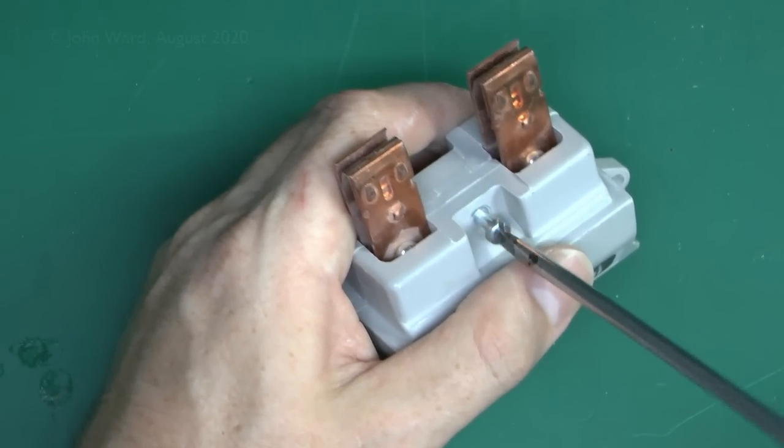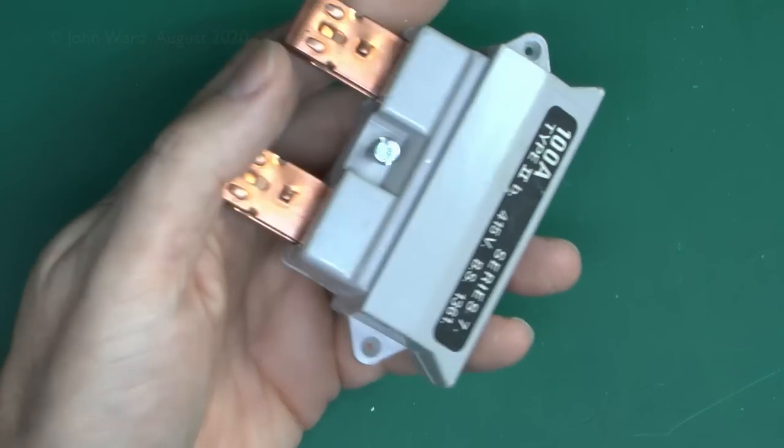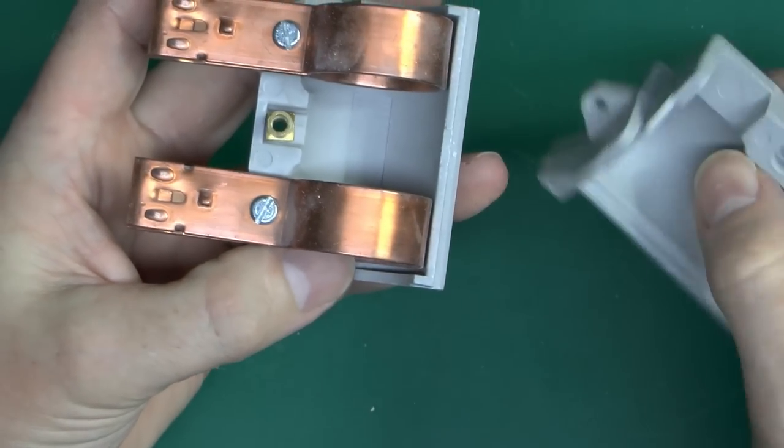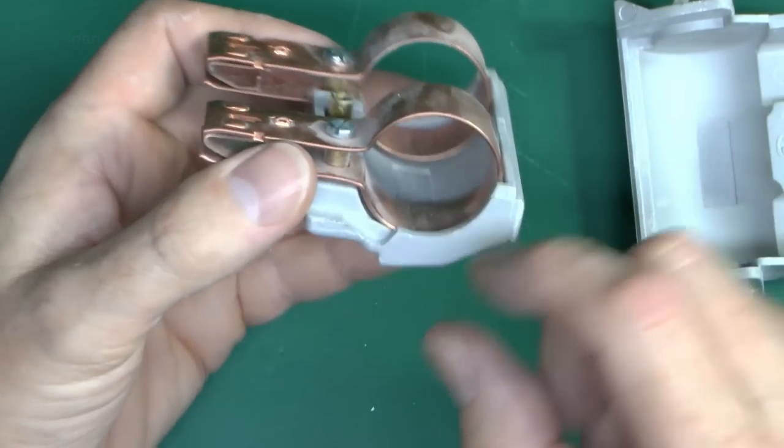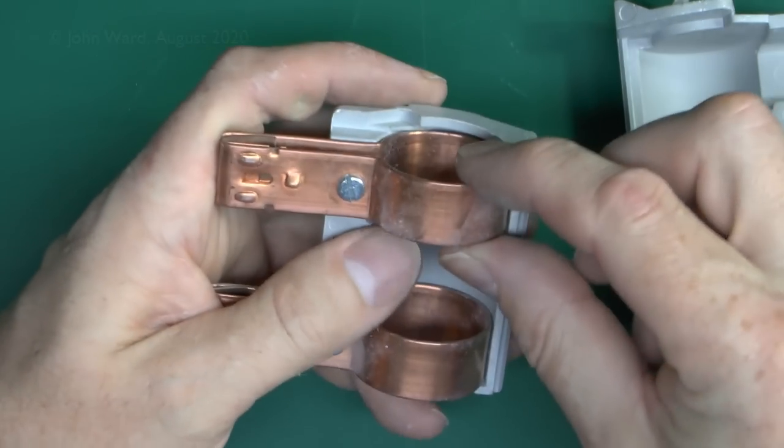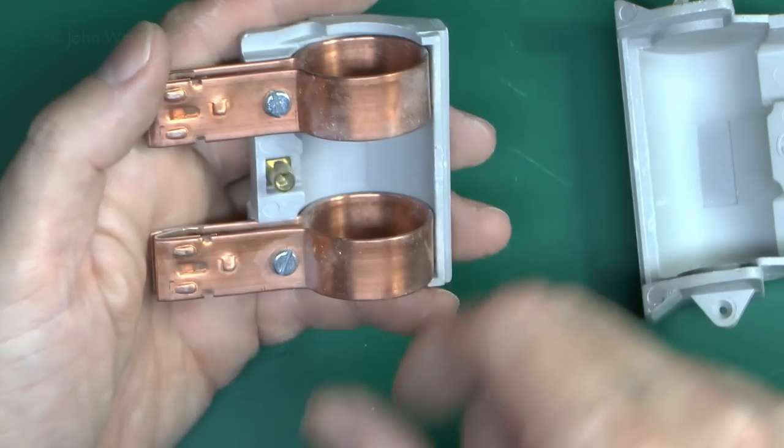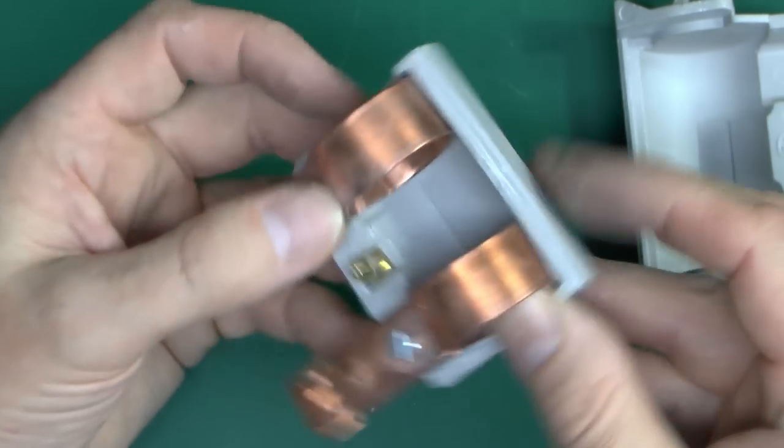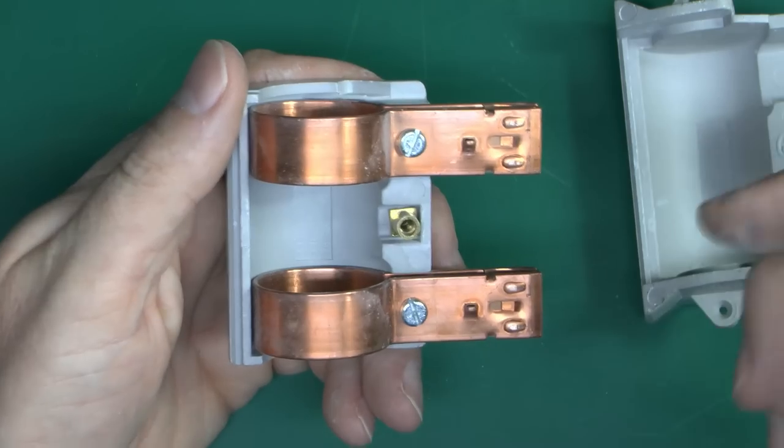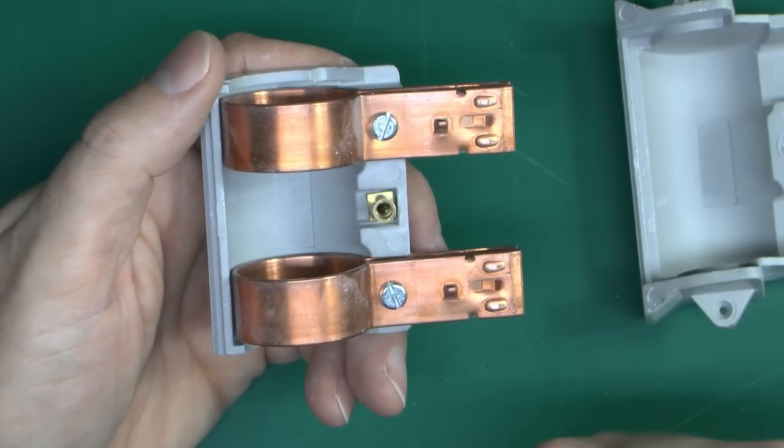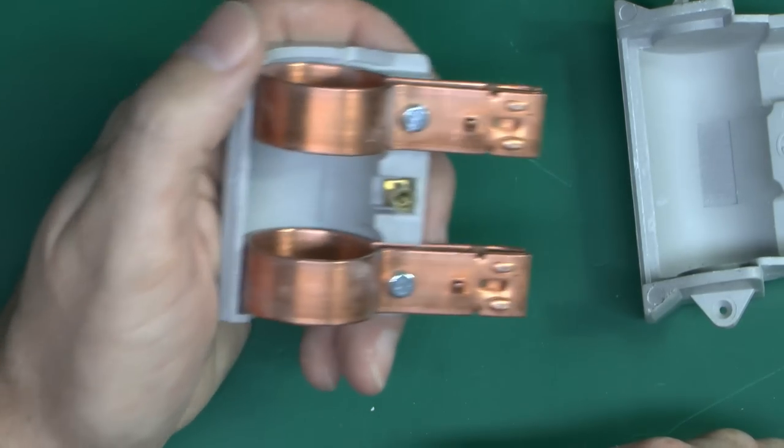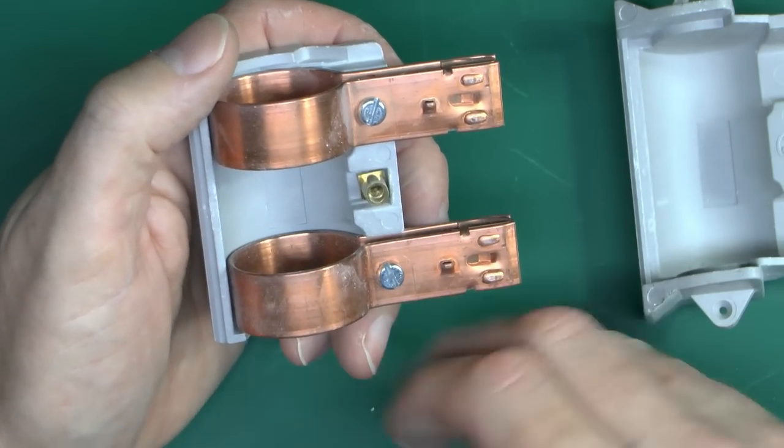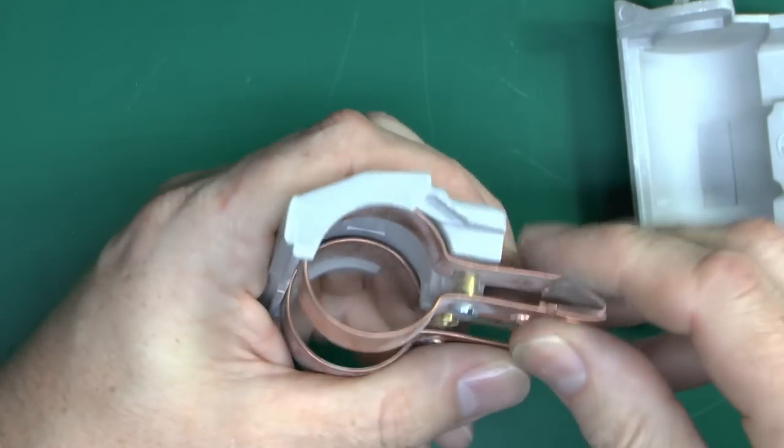Now this part is where the fuse goes, so it's just a single screw holding two pieces together. Comes apart like that, and then your fuse, which is a cartridge fuse, will actually go in these copper rings, so one ring on each end of the fuse, which is a ceramic body. These are very high rated for rupture capacity, so that when a fault occurs, this will actually reliably break it, even if there might be thousands of amps of a fault occurring. Hence made of a high durability ceramic material, and they're sand-filled as well to quench any arcing that goes on.